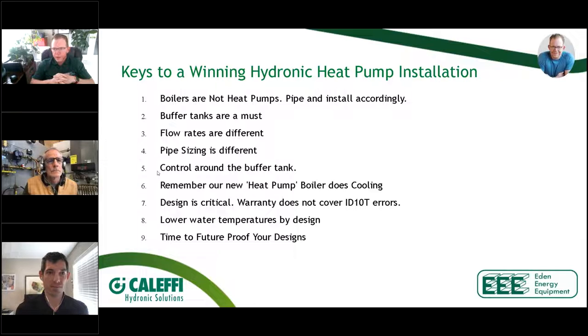The biggest thing I like to always reinforce, and Max and Bob can speak to this as well, is boilers are not heat pumps. Do not pipe a heat pump like you would a boiler. They have different requirements for flow rates. They have different pressure drops. They have different delta Ts. If you do, in fact, pipe a heat pump like a boiler, you're going to get a lot of experience because it's going to fail and you're going to have to redo it. And hopefully when you redo it, you'll pipe it accordingly and everything will go smoothly.